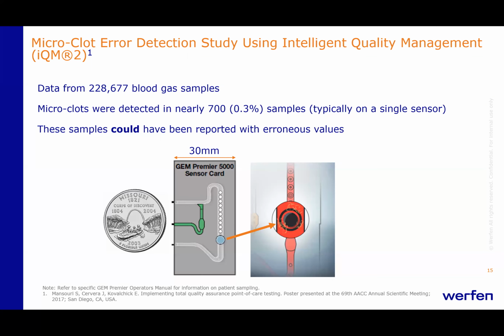I point your attention to the middle graphic there, which shows a GEM Premier 5000 sensor card. The circles are the actual sensors, and as you can see, it's approximately a 30 millimeter card. So the sensors are approximately 1 millimeter in diameter. The image on the right shows a graphic depiction of how microclots could settle on a sensor and subsequently affect the values.